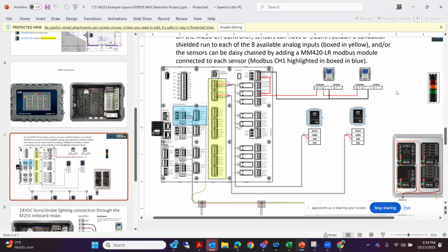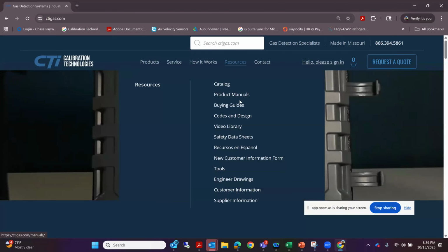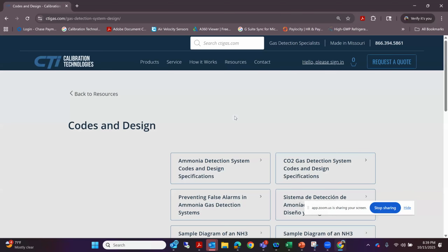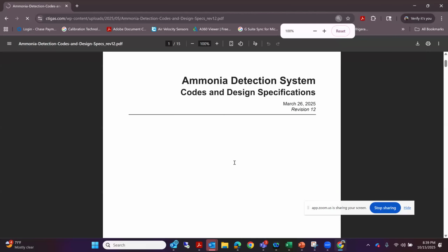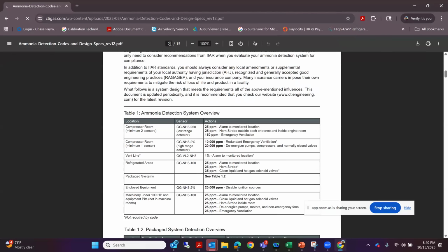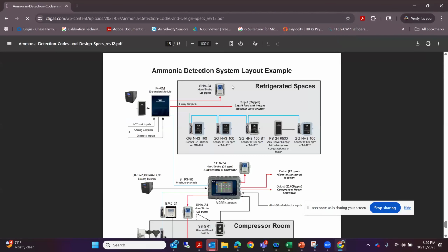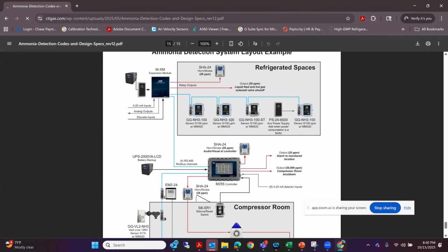And to back up that many horn strobes and keep them going as well, because you've got to be able to keep the lighting going if you're going to keep the sensors going. What good are the sensors if you don't have something telling a guy not to walk in there and into liquid on the floor? So we're powering everything with 24 volts, and we put the UPS on this system. And that UPS that you're seeing in the design documents, it's not there to allow this system to run forever, right? It's not even there to let it run for the 24 hours. It's really there to take the switch gear bang off, of that dedicated branch circuit that's kicking in and powering this UPS right here.